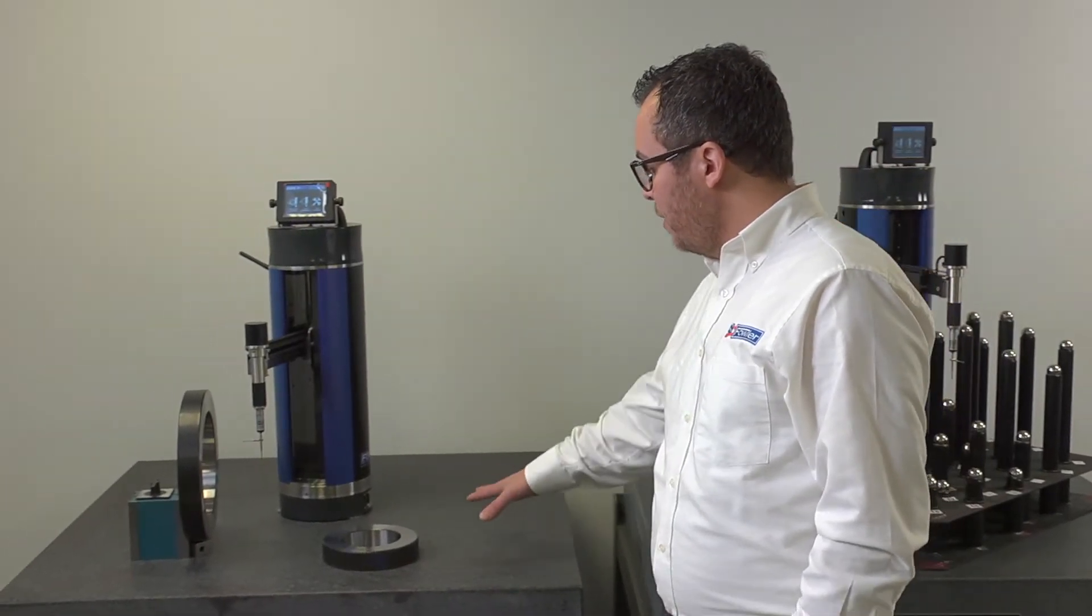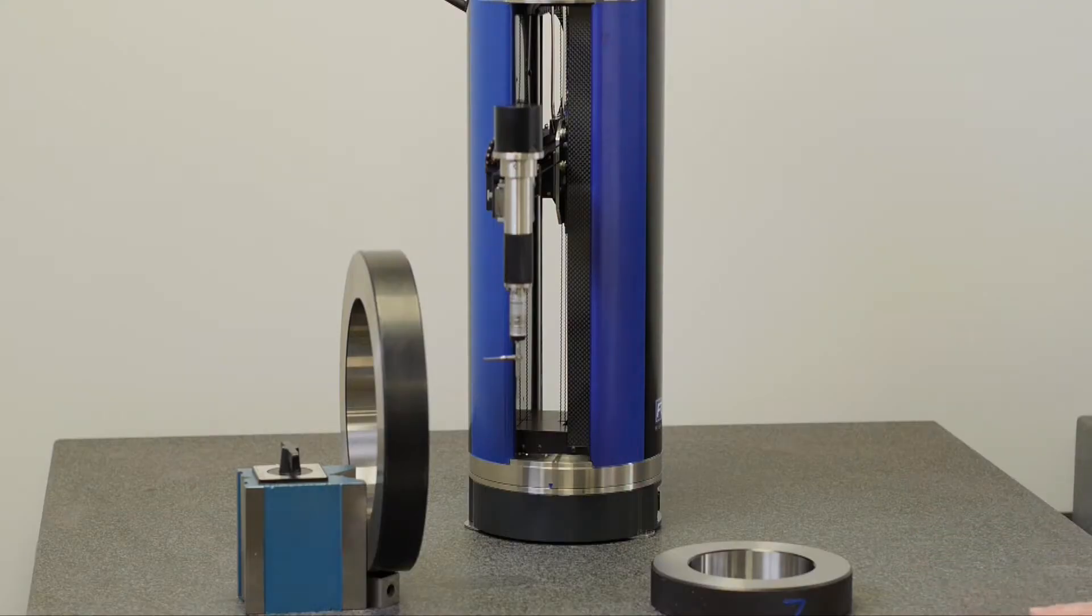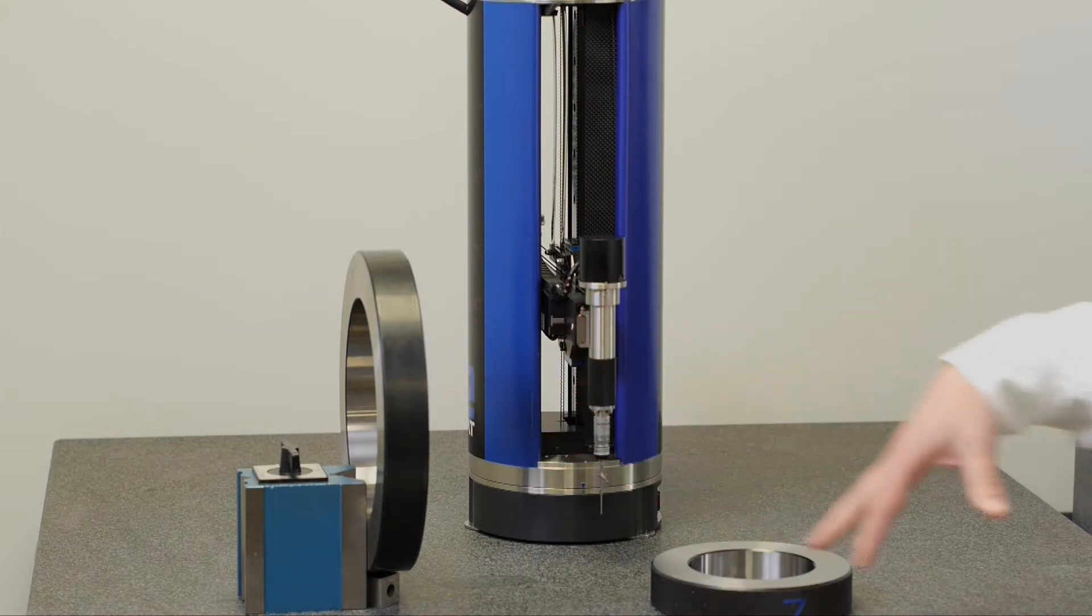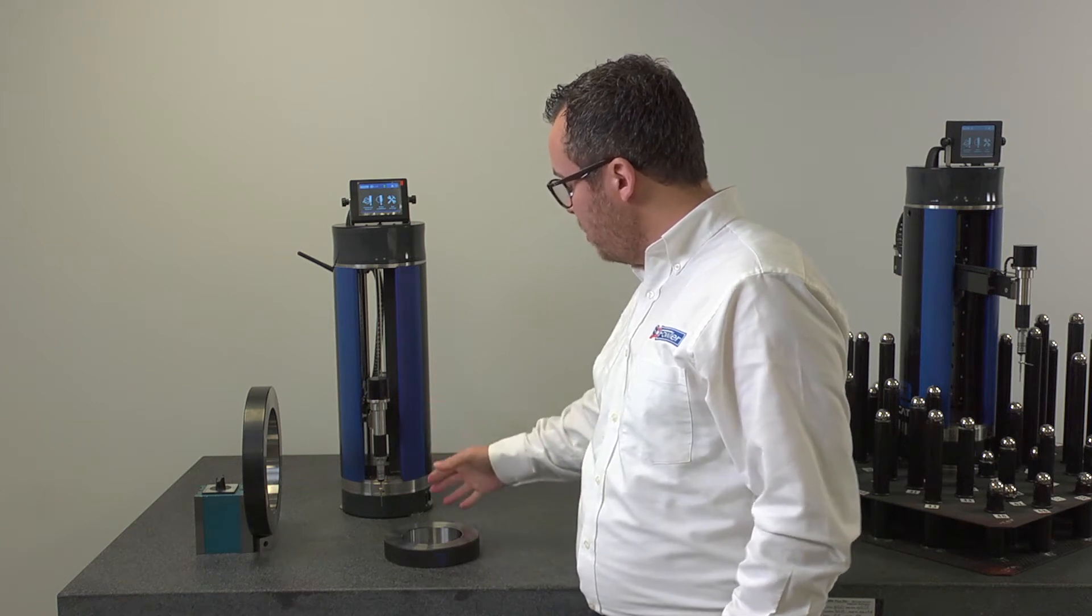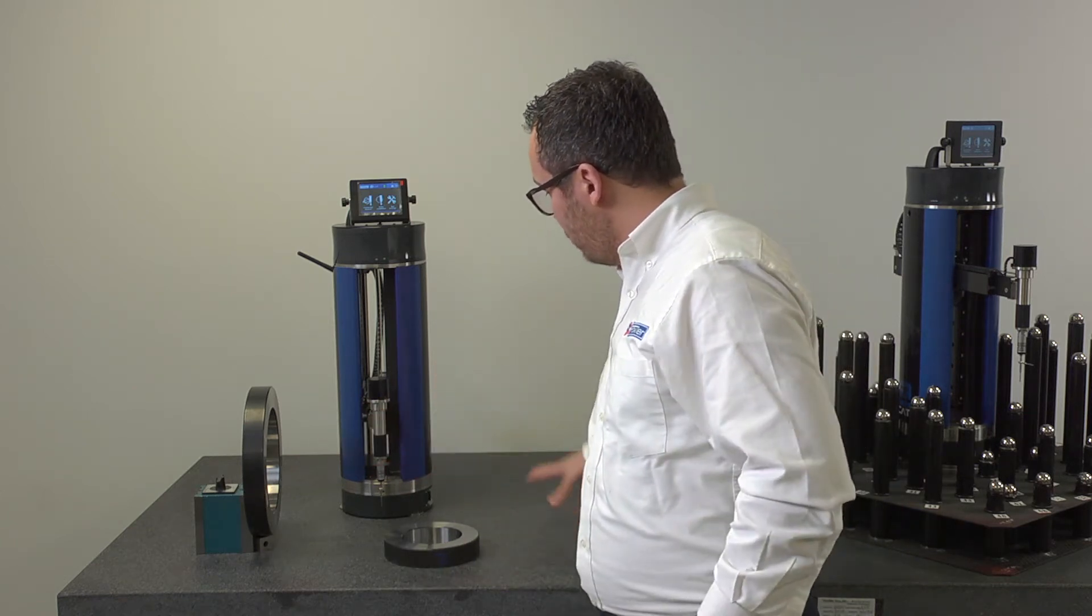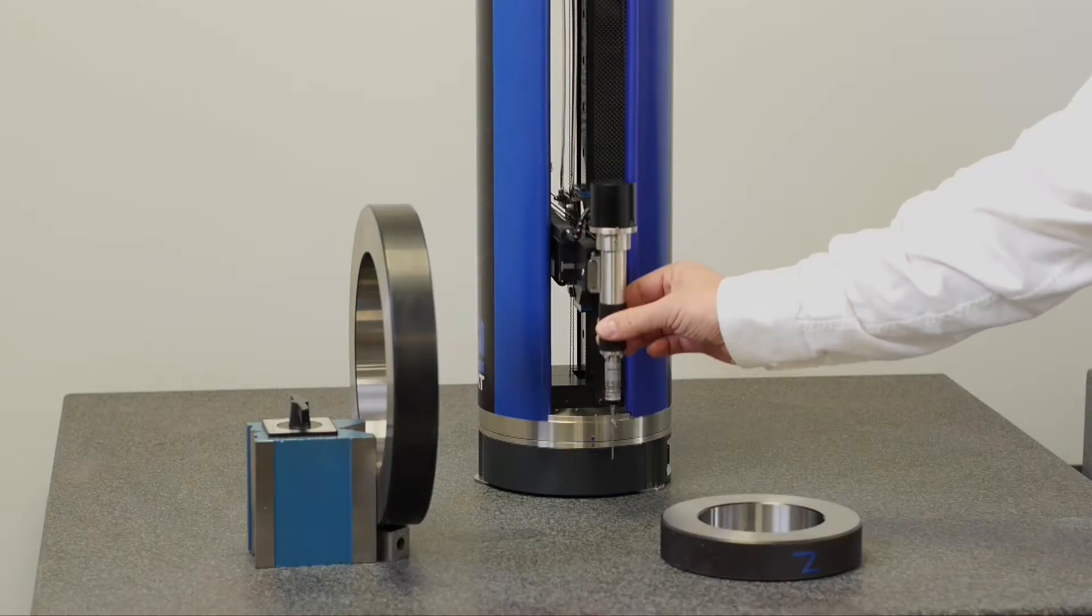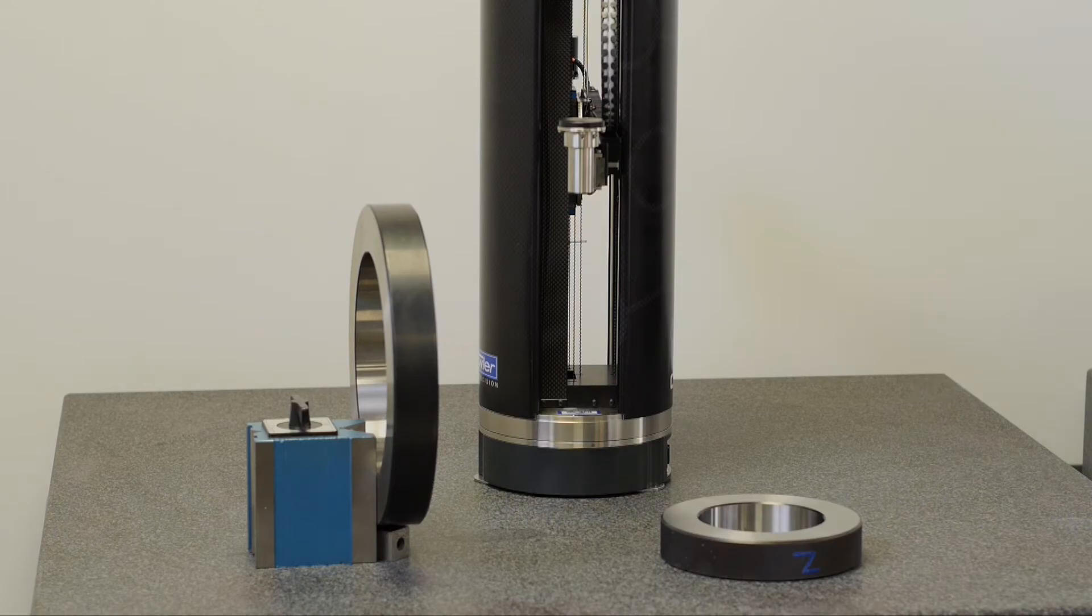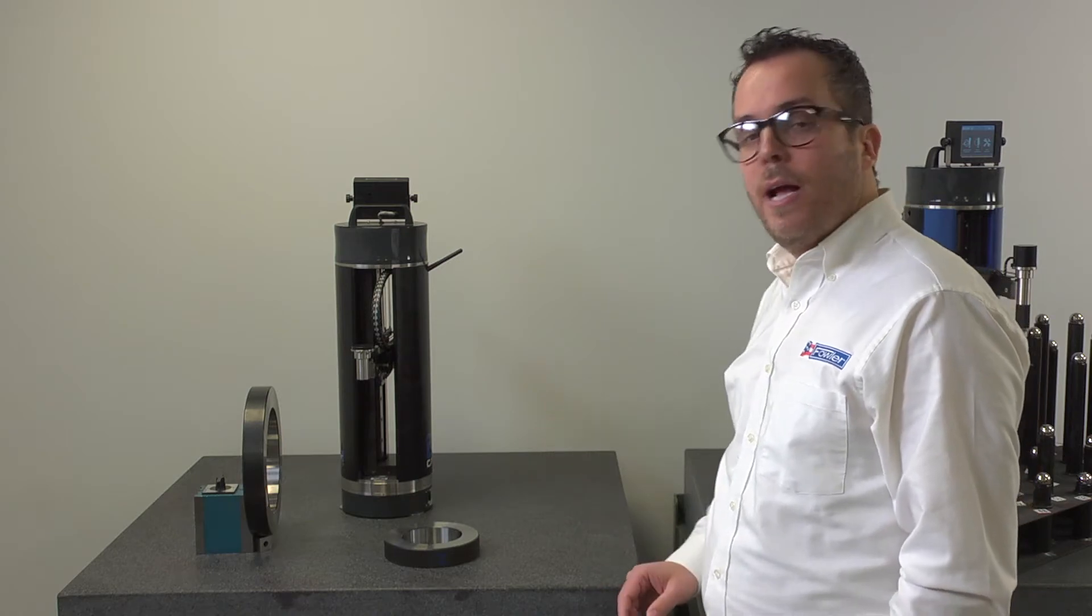We use three artifacts for calibration. The first one is a granite surface plate. It's actually a AAA surface plate and we check for flatness by measuring the whole plate in two locations. The first location will be the Zcat facing towards me which we call the zero degree location. We measure 360 degrees around Zcat all of the surface plate and we rotate the Zcat 180 degrees and start remeasuring the plate again. By doing that we will get our plane which we use for our calibration.